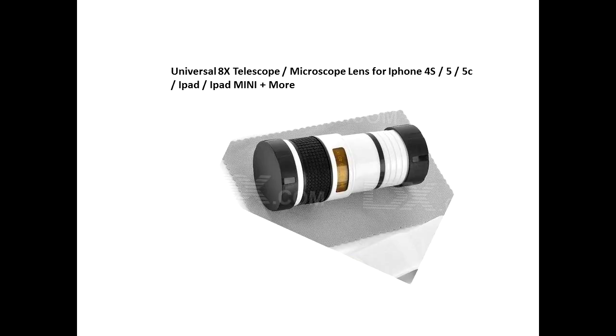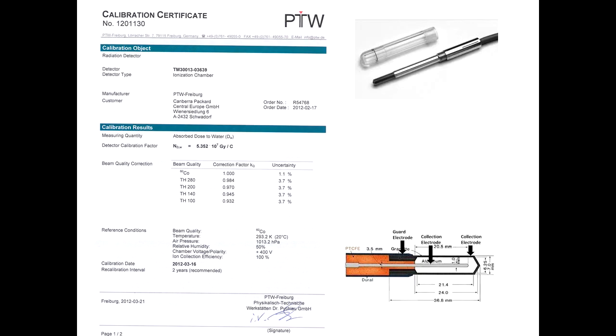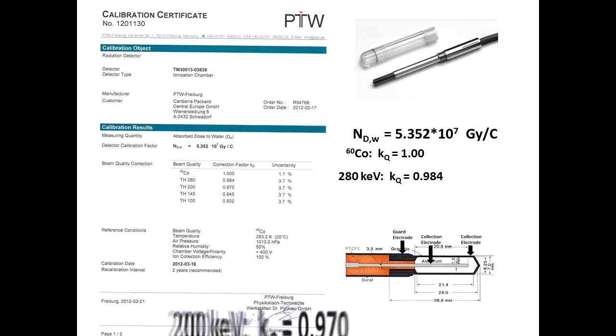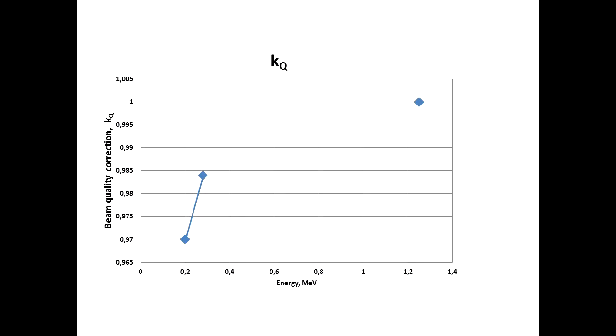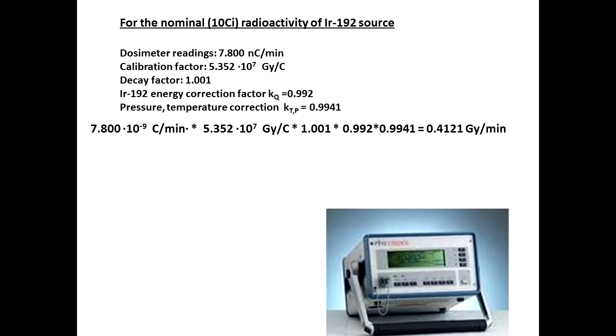To distinguish the thin tip of the measuring device, we use a universal mount with an 8 times magnification telescope for iPad together with a lens of +8 dioptres in order to reduce the focus distance for all this optical system. One of the parameters of the Farmer ionization chamber is the calibration factor for absorbed dose to water. The energy correction factor for the chamber we found by interpolating its energy correction factor from the calibration certificate.